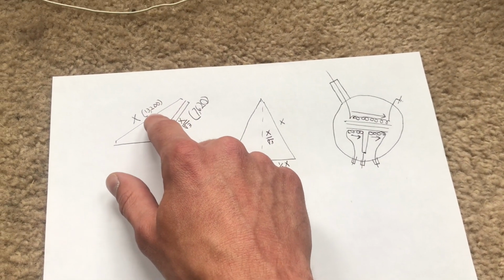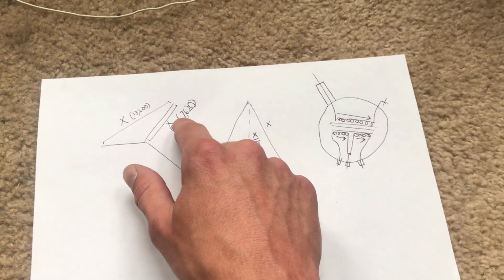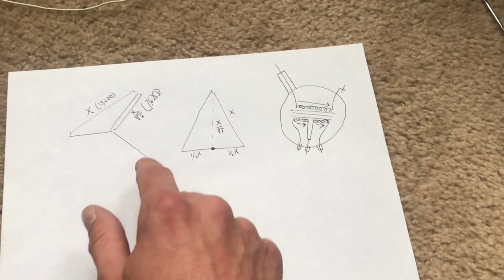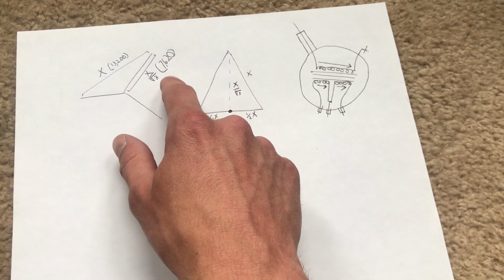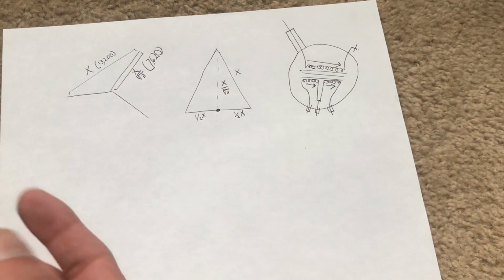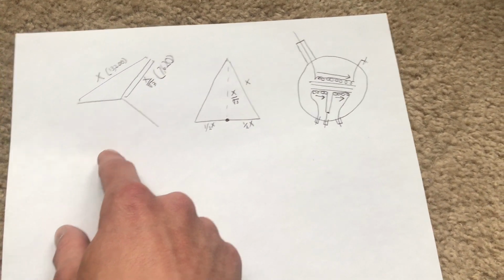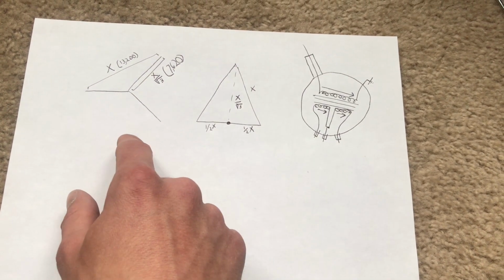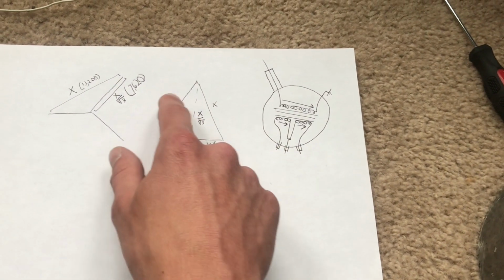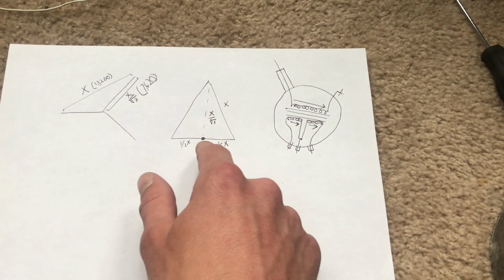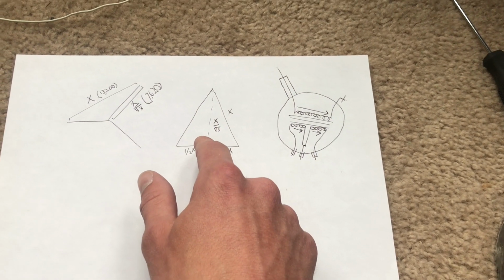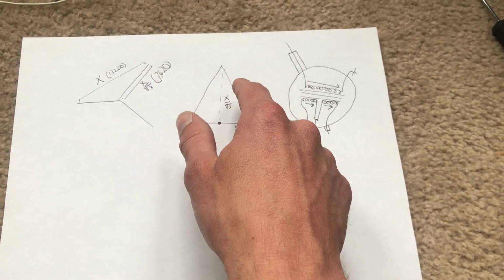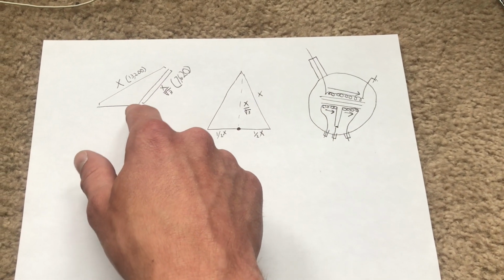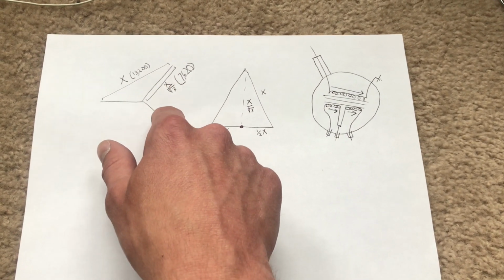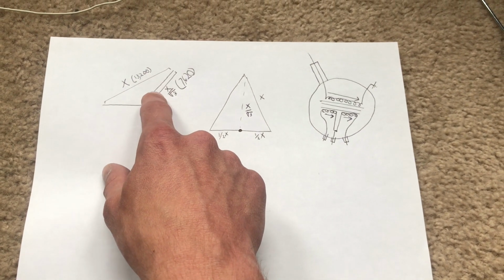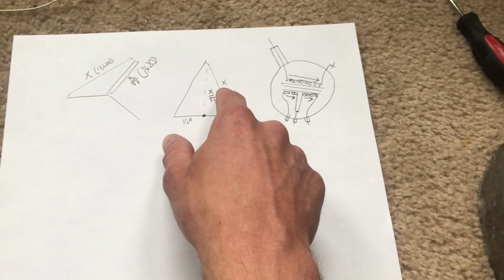Such as a very common voltage is 12470 Y 7200, and that dates back to the days of the Rural Electric push, where most systems that were installed were a 7200 delta, so 7200 between each phase. But then people realized that you could connect them in a star configuration, 7200, 7200, 7200, and it would be 12470. It'd be more power, and you wouldn't have to upgrade the insulators.